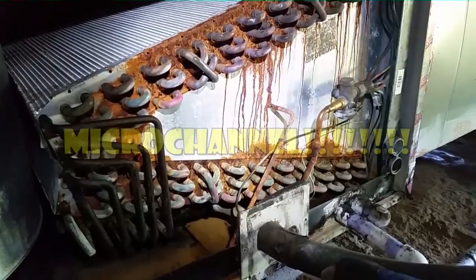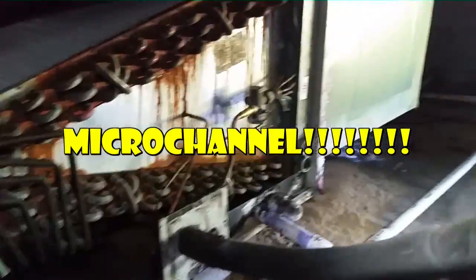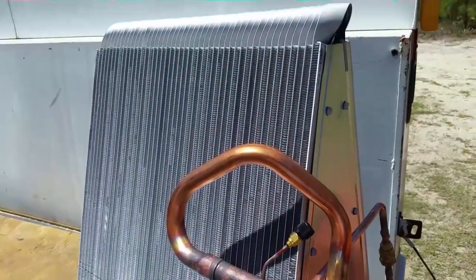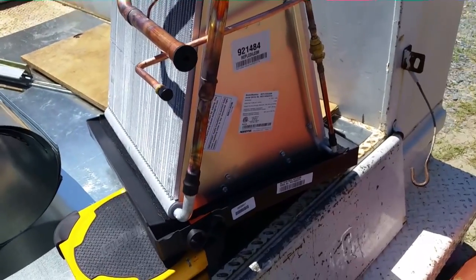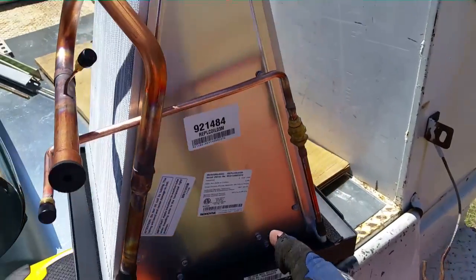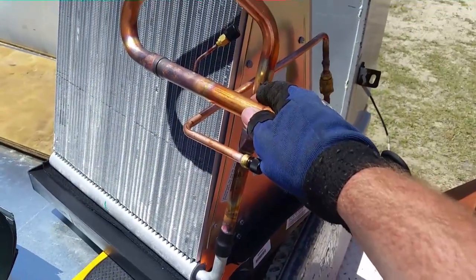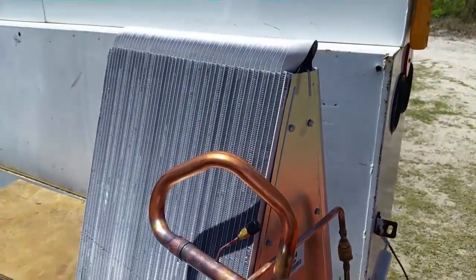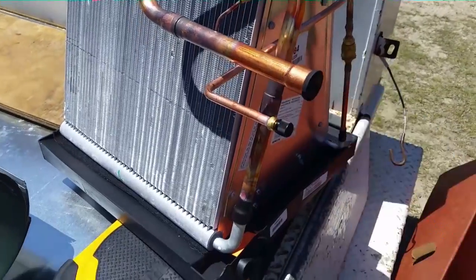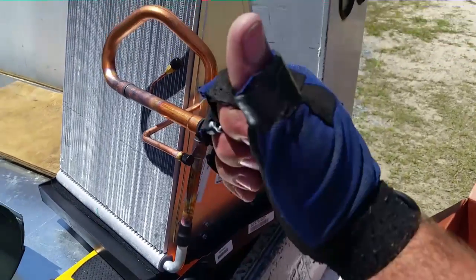Of course the Nordyne replacement will be micro channel. Here's our micro channel coil in all its glory. It's a single pass coil — one line goes in, travels throughout the coil, and one line comes out. There's no manifold with different branch circuits, just one pass through. Very interesting. But it does have an orifice in it, so that's what we're using.